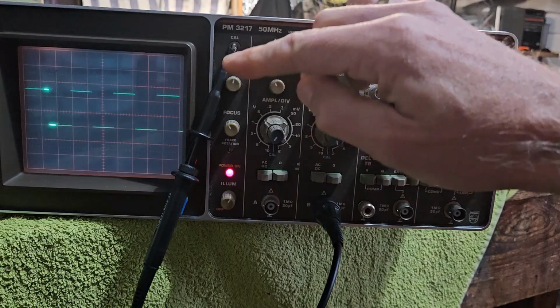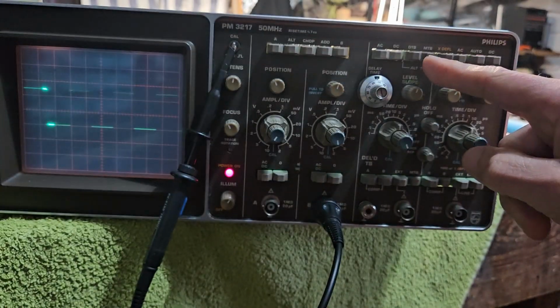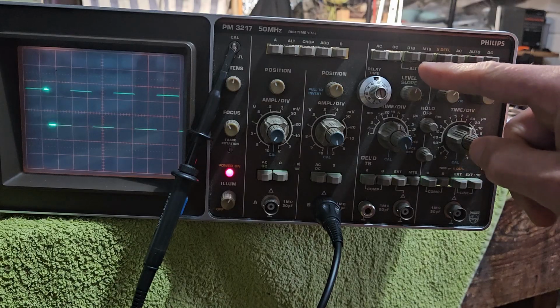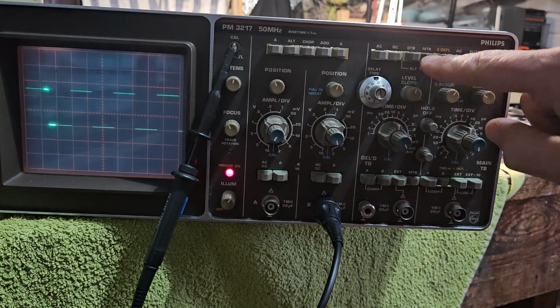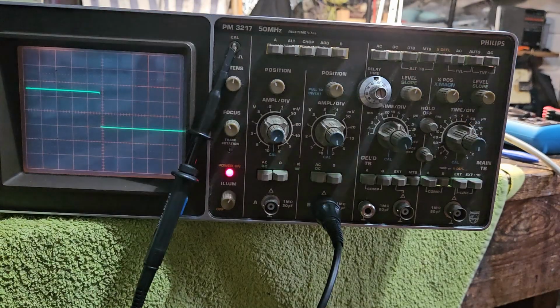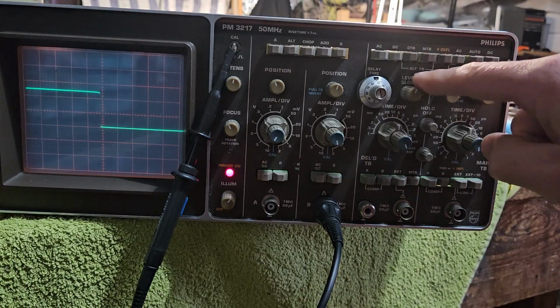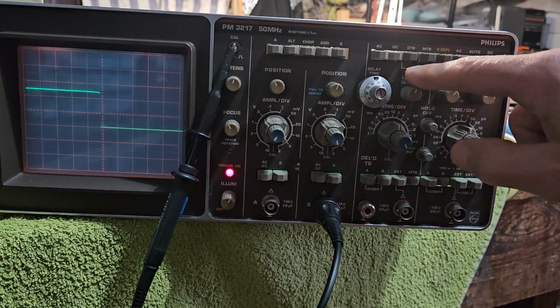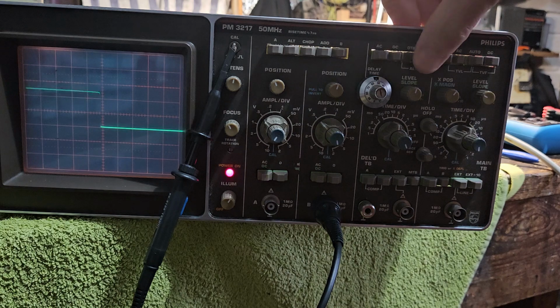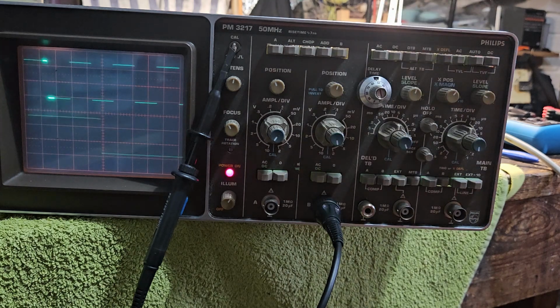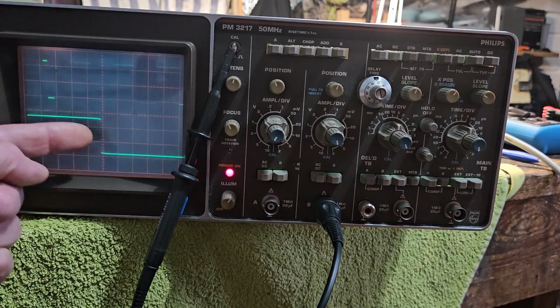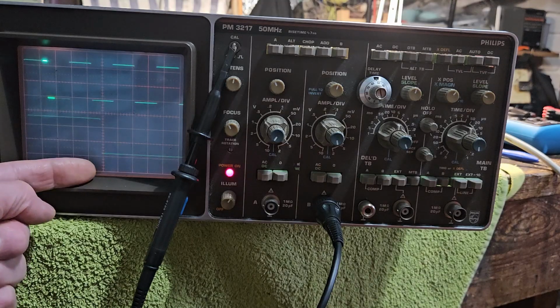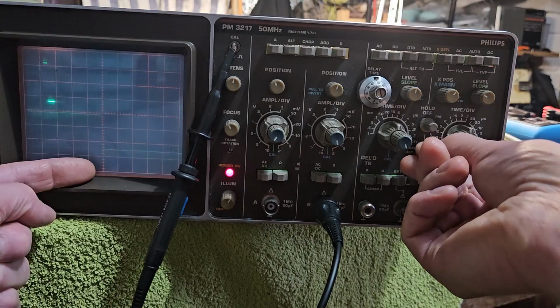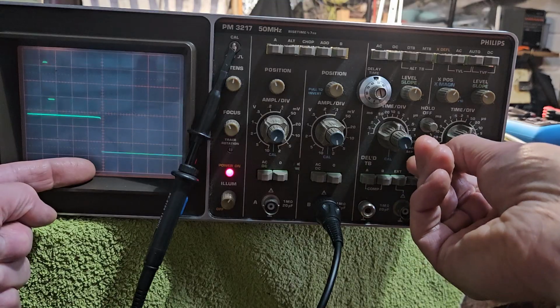Okay, so that is kind of selecting, if you like, the bit of the waveform that we are interested in. So in order to actually see it, we then switch from the main time base here to the delayed time base, and that there is the edge of that main waveform. And if you depress both of these buttons together, you get the alt time base mode, which, as you can see now, gives you the main waveform with the selected part and the display of that selected part. And then you can adjust the separation with this control.